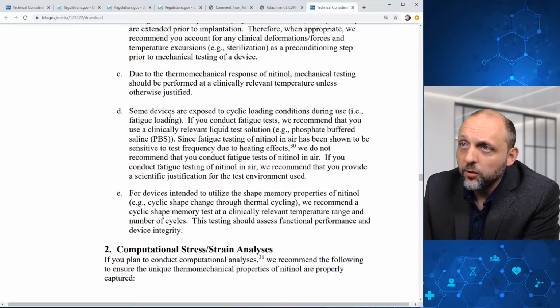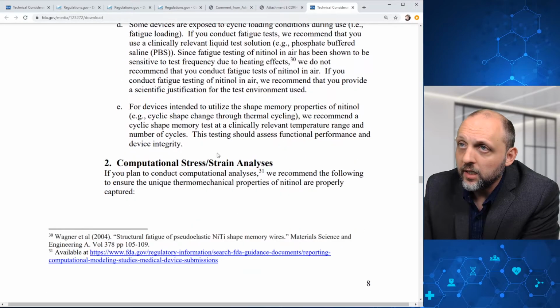Some devices are exposed to cyclic loading conditions during use. If you conduct fatigue tests, FDA recommends that you use a clinically relevant liquid test solution. FDA does not recommend that you conduct fatigue tests of nitinol in air. And if you do so, you should provide a scientific justification.